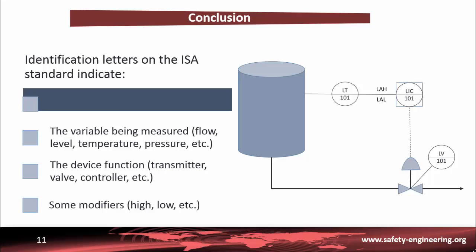The example shown at the beginning of this part can be analyzed in more detail. The first letter for all devices is L, so this control loop refers to level. A level sensor is connected to the tank. A transmitter converts the raw signal at the output of the sensor to a normalized electrical signal — a 4 to 20 mA current loop. This standard signal is sent to a controller. Two alarms warn the operator if the level is too high (LAH) or too low (LAL). A controller with an indicator produces an output signal as a function of measurements and set points. This control signal is sent to the valve to adjust the flow rate and maintain a constant level equal to the desired value.